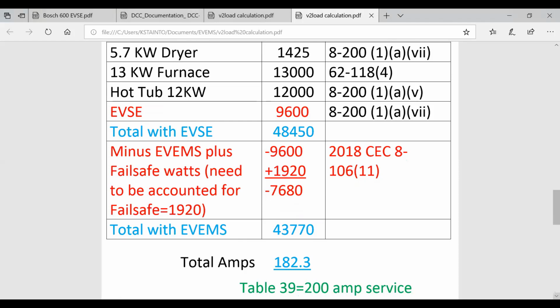You can see we have the EVSE at 9,600 watts. Now we've included our EVEMS, but because I said the fail-safe was going to be 8 amps, 8 amps at 240 volts is 1,920 watts. So we won't be able to completely cancel out the EVSE with the EVEMS. What we're going to do is deduct everything but the fail-safe value. In this case, 9,600 minus that 1,920 gives us a difference of 7,680.